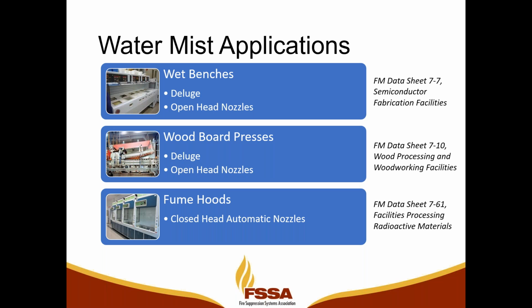But wet benches are a Class B type hazard where we've got little vats of either acids or solvents that we're using to clean or etch electronic parts. And we protect these with a deluge system where we're going to flow water out of all heads simultaneously. We're going to protect below the cabinet space, the working surface, and the above cabinet space. So we've got exhaust hoods here sucking the toxic fumes out of the workspace, and we've got to take that into account in our protection scheme. And FM data sheet 7-7 tells you everything you would want to know about protecting wet benches.